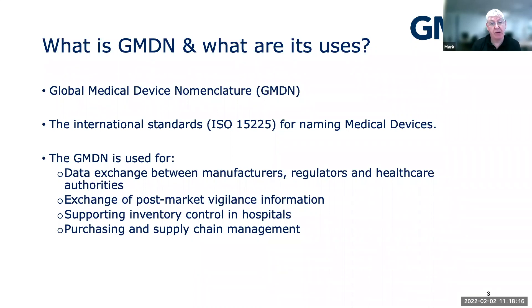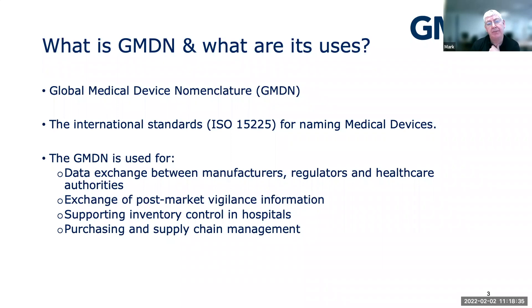GMDN is used primarily to exchange data between manufacturers, regulators, and health authorities or hospitals. It's also used to track problems or opportunities when using medical devices — what we call vigilance — and to support inventory control, so you know how much of a certain type of product is available, and to support the purchasing process to identify the type of product you're looking for.